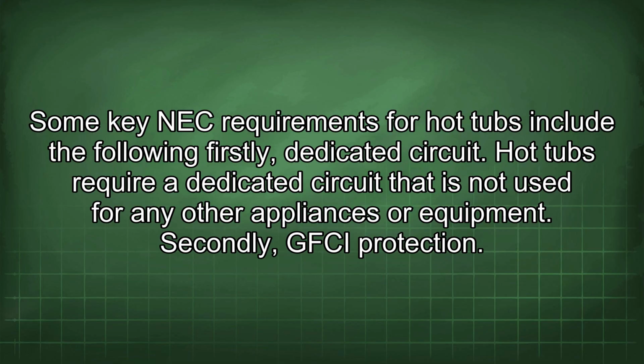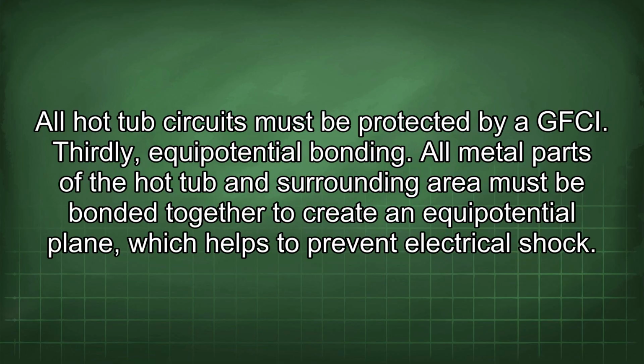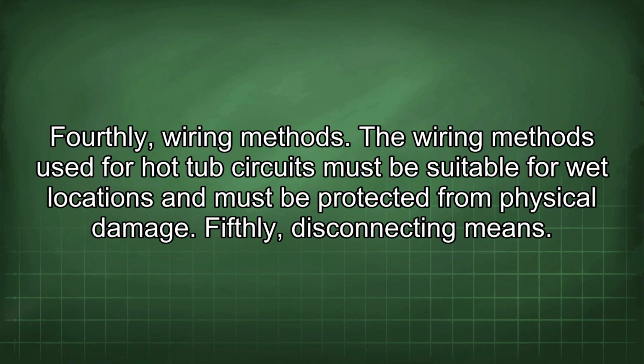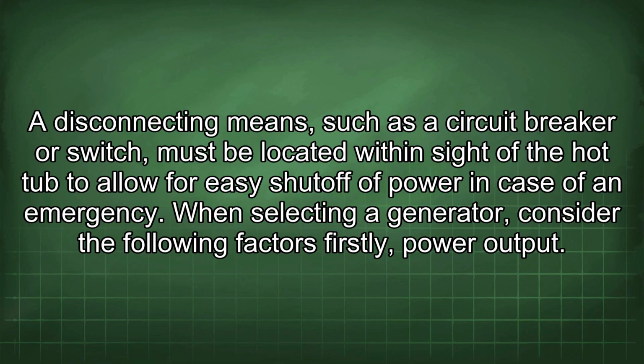Firstly, dedicated circuit. Hot tubs require a dedicated circuit that is not used for any other appliances or equipment. Secondly, GFCI protection. All hot tub circuits must be protected by a GFCI. Thirdly, equipotential bonding. All metal parts of the hot tub and surrounding area must be bonded together to create an equipotential plane, which helps to prevent electrical shock. Fourthly, wiring methods. The wiring methods used for hot tub circuits must be suitable for wet locations and must be protected from physical damage. Fifthly, disconnecting means. A disconnecting means, such as a circuit breaker or switch, must be located within sight of the hot tub to allow for easy shutoff of power in case of an emergency.